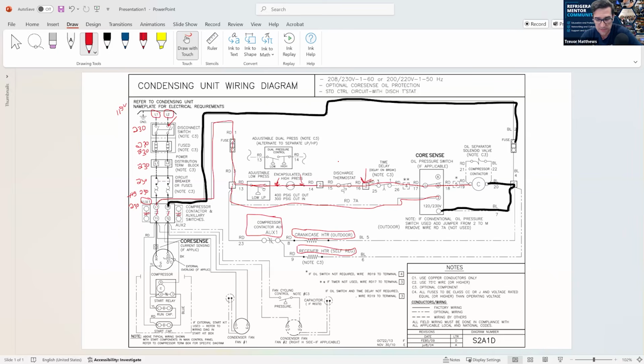Take a look at the system that you're working on and then go and get your meter and use the meter in the field safely. And do it like this. Start at the very first. I got 230 coming in. I go down through my disconnect. I go through my fuses. I go through my circuit breaker. I go to my compressor, across my compressor. Okay. Upstream of the compressor, I got voltage. Downstream, I got compressor voltage. The compressor's running. Great. So that's an awesome thing.